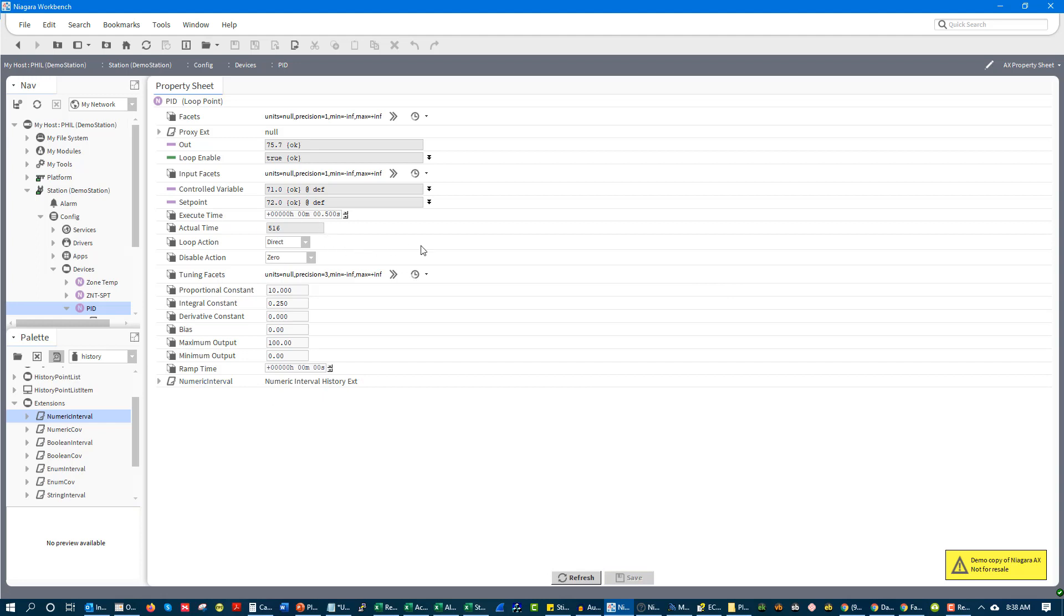And for things like heating, things like pressure, those would be reverse acting loops. So when you look at this, you've got to determine your direct acting or reverse acting. You've got to determine your proportional constant and you've got to determine your integral constant.